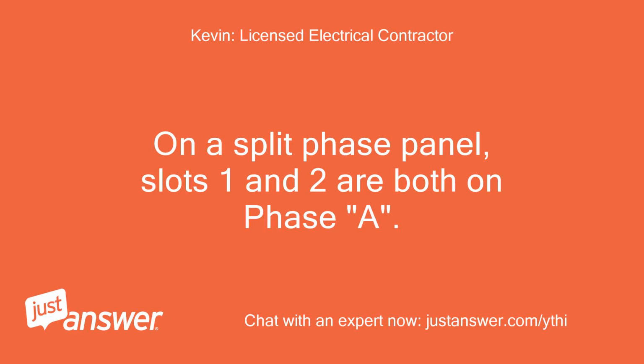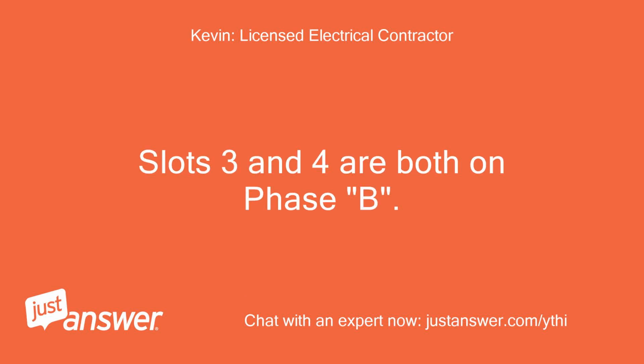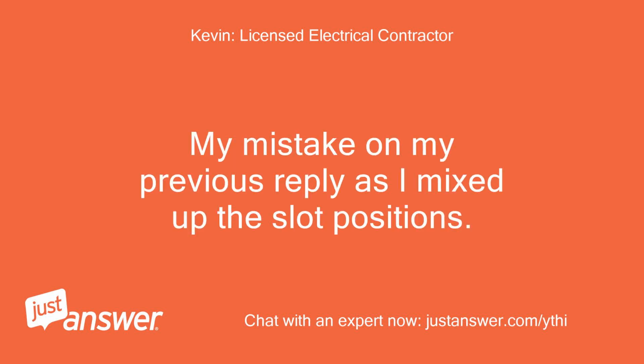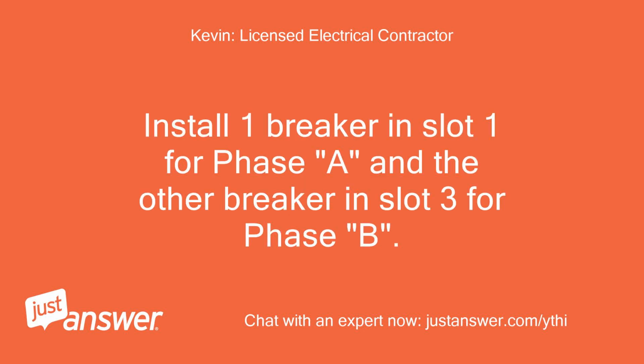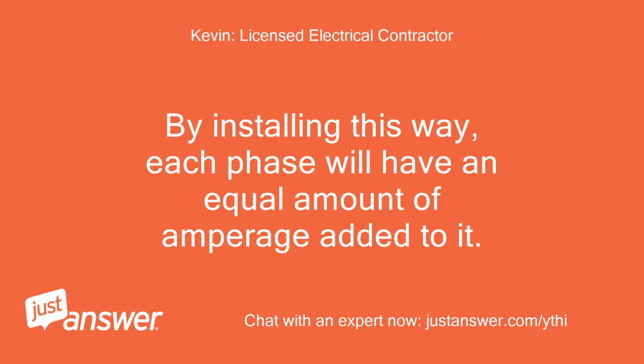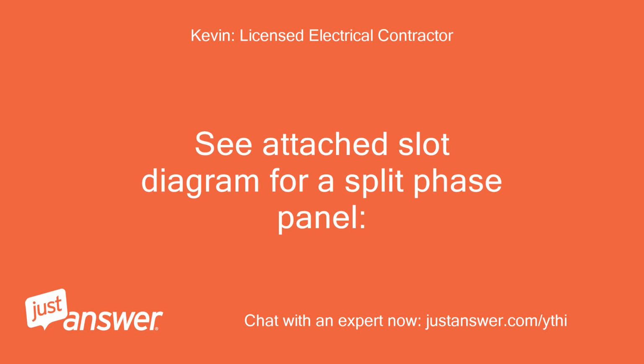On a split phase panel, slots 1 and 2 are both on phase A. Slots 3 and 4 are both on phase B. My mistake on my previous reply is I mixed up the slot positions. Install one breaker in slot 1 for phase A and the other breaker in slot 3 for phase B. By installing this way, each phase will have an equal amount of amperage added to it. See attached slot diagram for a split phase panel.